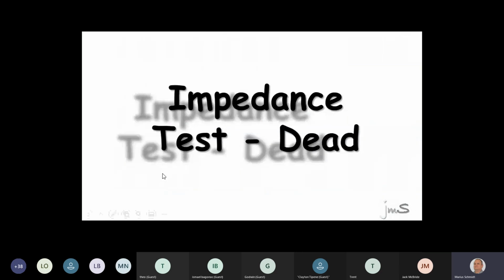Right. So before I do this test, you all agree the impedance test is there to ensure that if a fault occurs, the protection devices will operate within a certain time. Secondly, it will trip. And thirdly, it will trip safely. It's an important test, eh? But we only do an impedance test on sockets which are not on RCD.